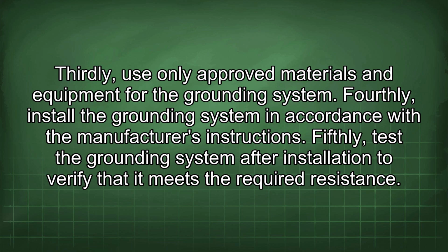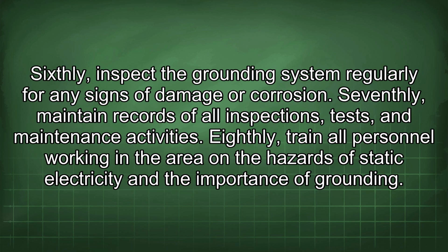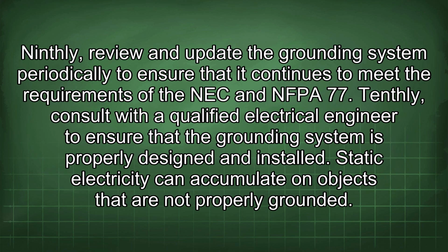Fifthly, test the grounding system after installation to verify that it meets the required resistance. Sixthly, inspect the grounding system regularly for any signs of damage or corrosion. Seventhly, maintain records of all inspections, tests, and maintenance activities. Eighthly, train all personnel working in the area on the hazards of static electricity and the importance of grounding. Ninthly, review and update the grounding system periodically to ensure that it continues to meet the requirements of the NEC and NFPA 77. Tenthly, consult with a qualified electrical engineer to ensure that the grounding system is properly designed and installed.